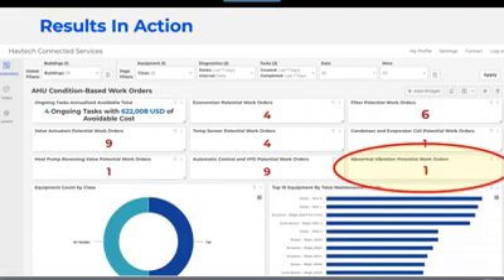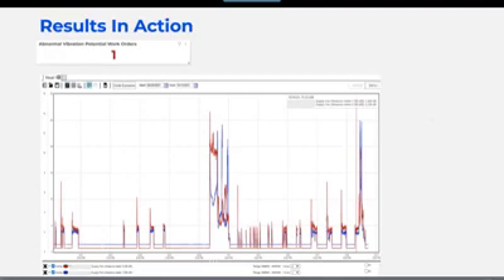The tool here highlights sensors on this critical air handler, serving a production floor, that measured vibration coming from the fan motor. When there are anomalies, the fan vibrates more, a sign something's wrong, probably with the bearings, which could lead to failure. Here's a case where the FDD tool caught that and signaled a vibration issue on this equipment.